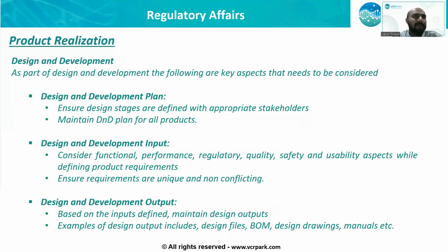We ensure the right people are identified. We ensure the appropriate stakeholders are defined. The plan for every product that we might be developing shall be in place and updated as and when needed. Once the plan has been defined, we move towards implementation of the plan. So the next thing that comes into the picture is ensuring that we have the right requirements being defined for the device. The design and development inputs is where we collect those requirements.